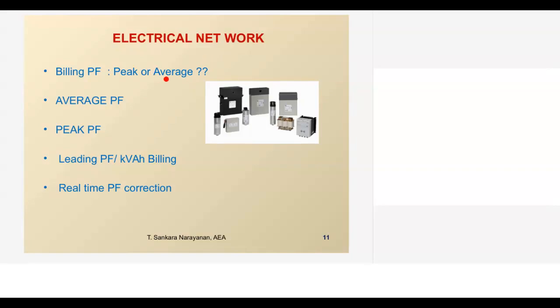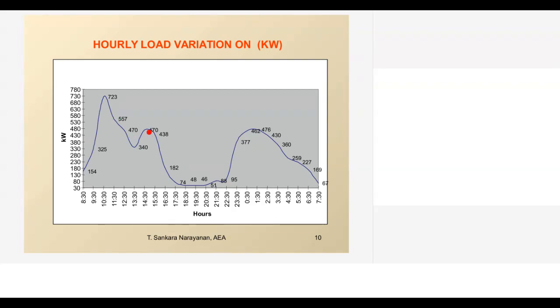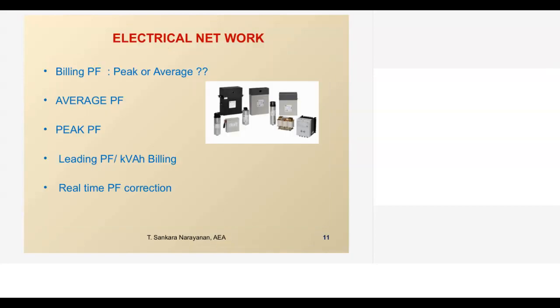Especially in an engineering network, if you see, certain capacitors are already kept on the line, so I am able to maintain my average power factor. Whereas when the peak load is coming, how my power factor compensation works has to be reviewed. This is what is required in the case of a purely engineering network. An engineering network will have a load curve like what we have seen, with so much variation, whereas in a process plant the load variation will be very less. So wherever we are doing an audit of an engineering network, we need to review the billing power factor and the peak power factor.